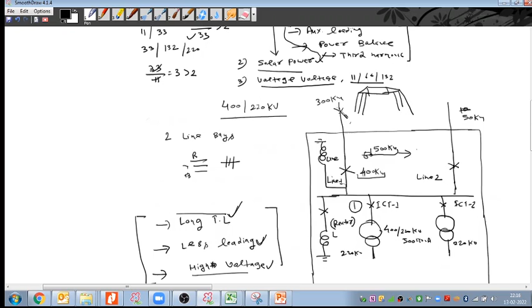Shivam, as I said, when I use the line reactor and when I use the bus reactor: suppose we have four or five transmission lines, or suppose we have two transmission lines, but out of the two, one line is a longer transmission line, say 300 kilometers, and the other is a short transmission line, say 100 or 50 kilometers. So which line will inject the reactive power? Obviously, this line will inject the reactive power. Am I correct?